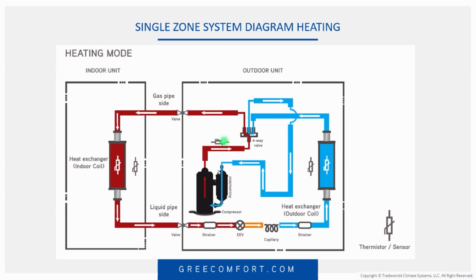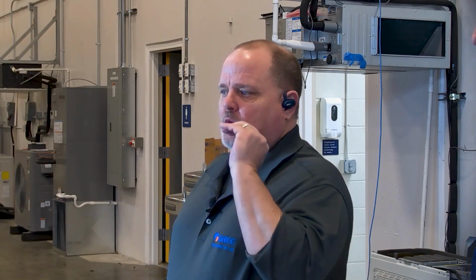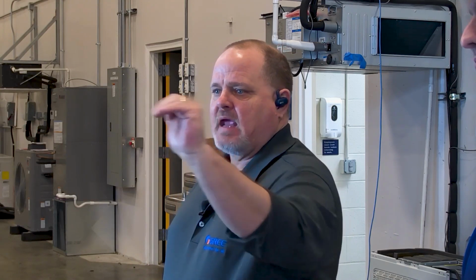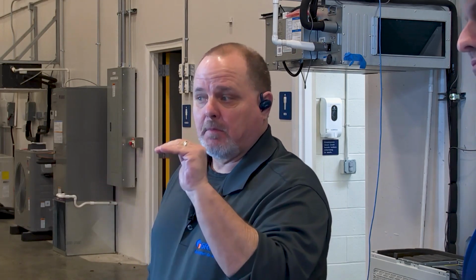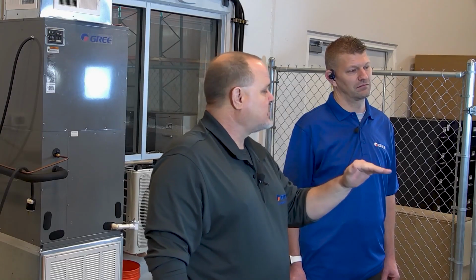So with that said, you've got your basic components here. Now what they're doing is building on that by throwing these thermistors and everything in there, monitoring the operation of the unit and controlling the speed of the compressor and the fan motors to try to satisfy the load more quickly or more slowly, depending on what it's trying to do. And I say more slowly specifically. Mini splits will do everything they can to not shut off. The whole energy efficiency savings comes from that machine running at a very low rev and maintaining the temperature in the house. That's where you get your efficiency from. So the whole idea is set it and forget it. Let the machine do its thing.